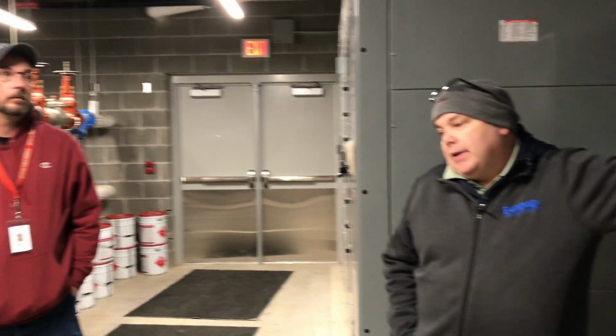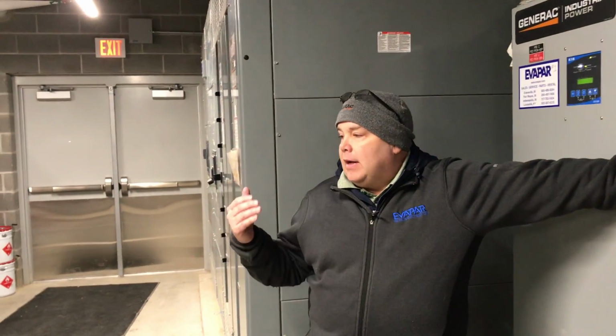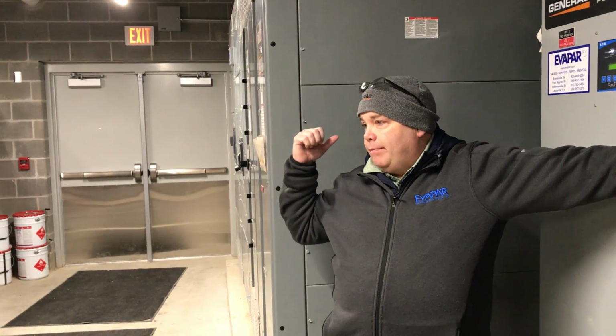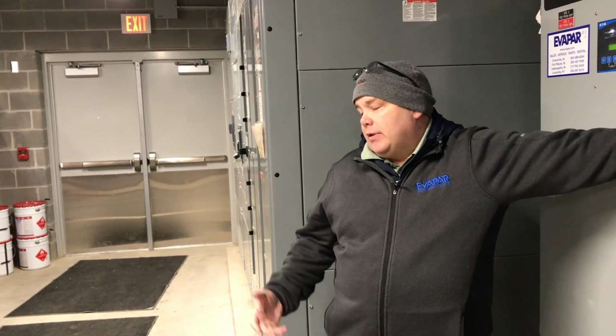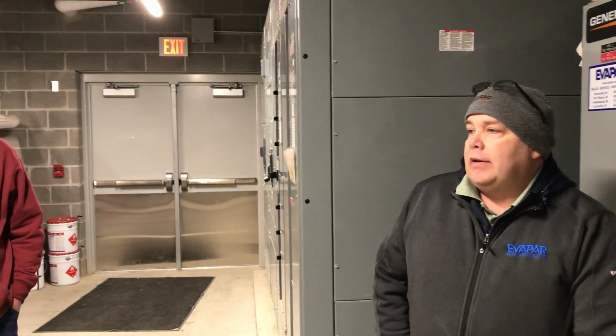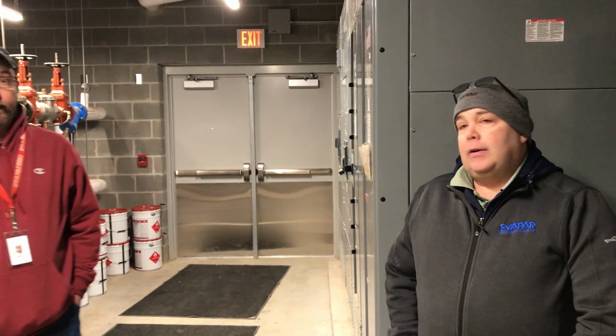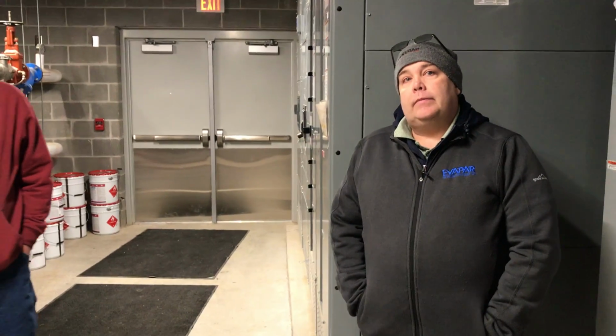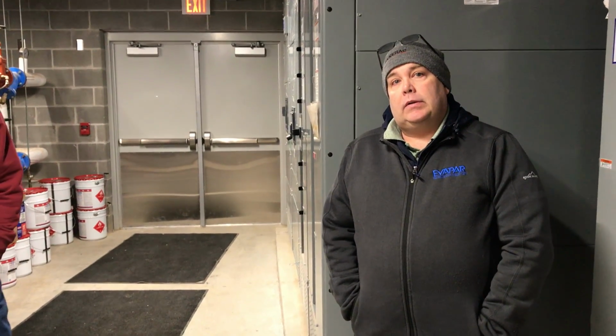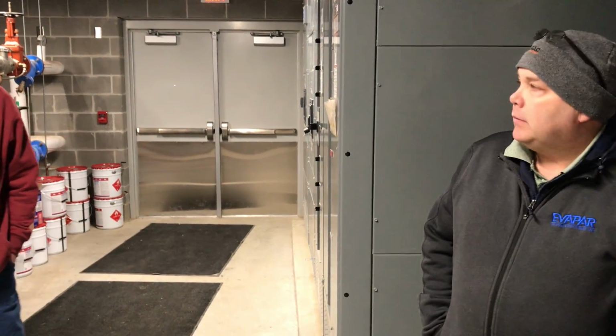It's just part of NFPA 110. If it loses the battery charger, it must annunciate, just because of the battery problem, it's not going to start. That's why they want it. Well, one way it's gonna let us know we lost power. Well, that's the only time it would come in is if we actually have a power outage. On an exercise, we don't exercise with load, so it won't go off.